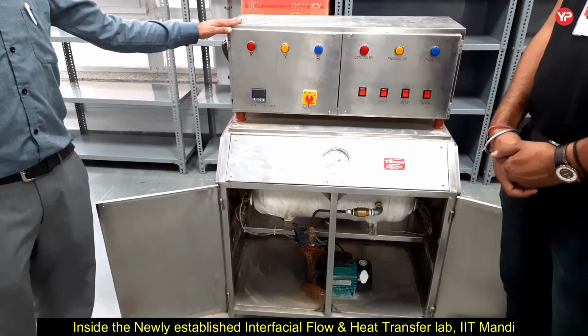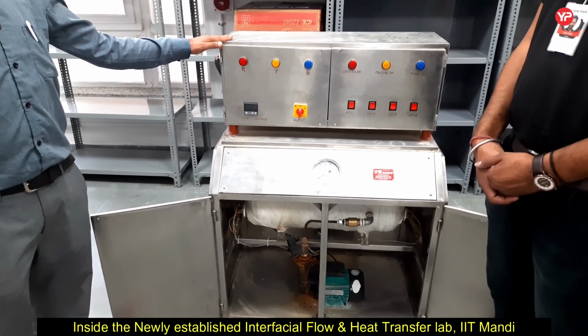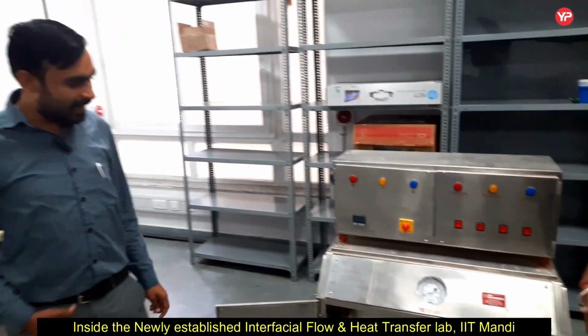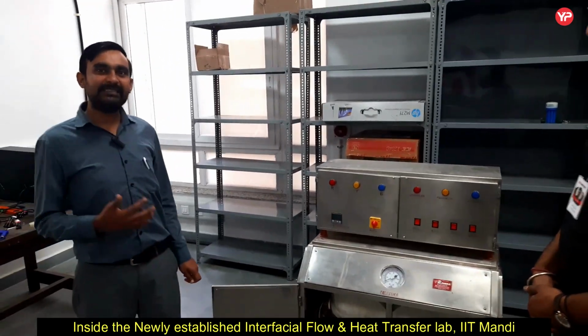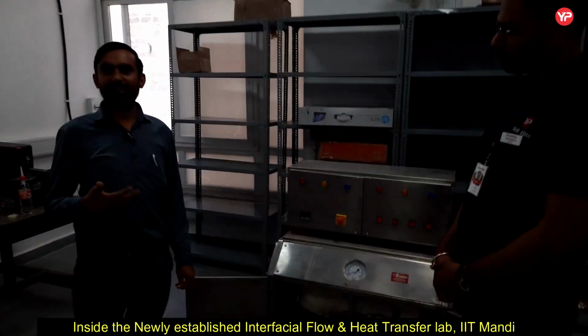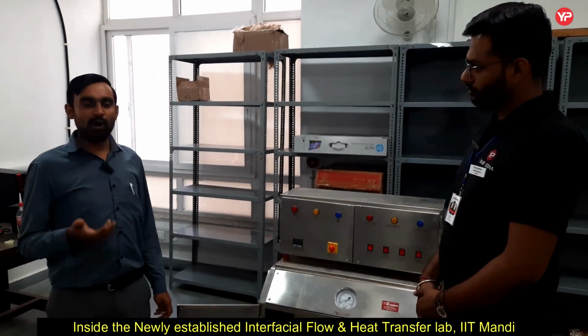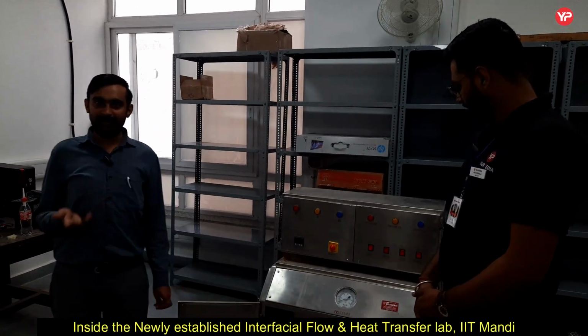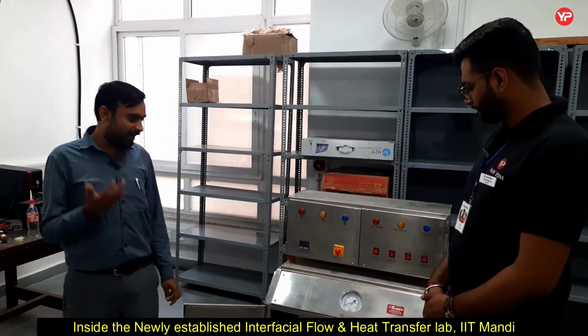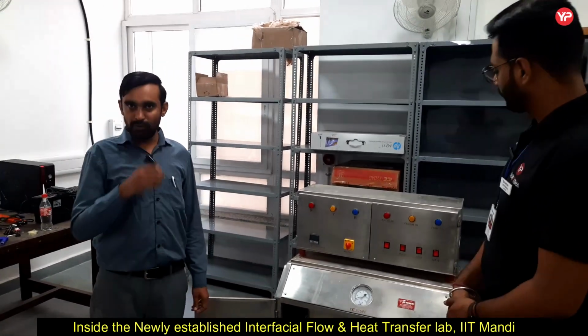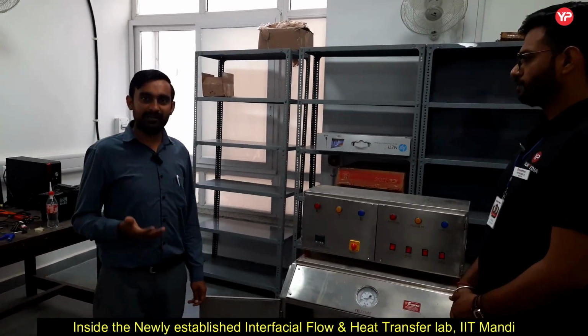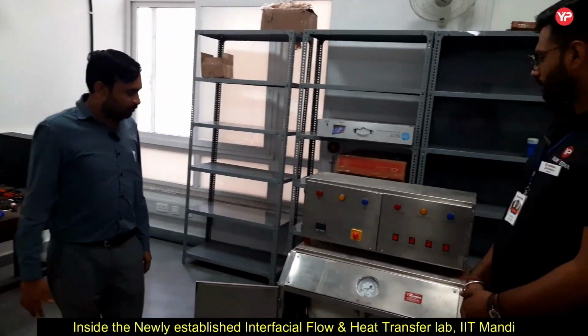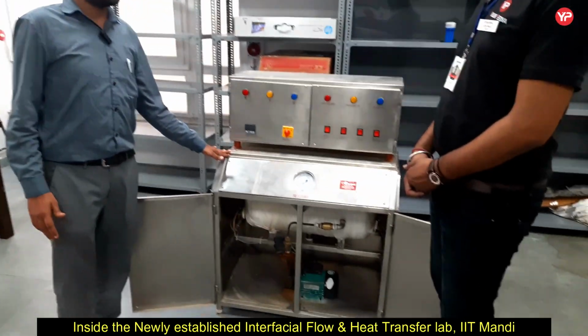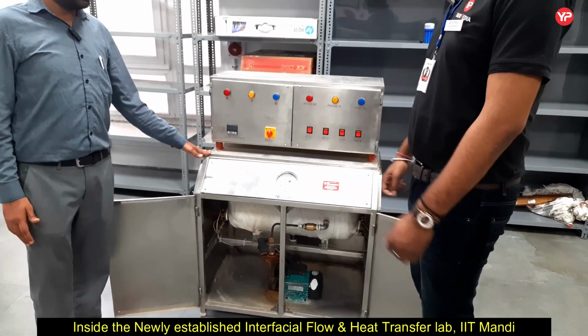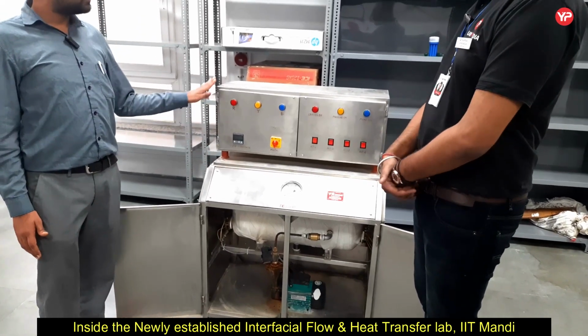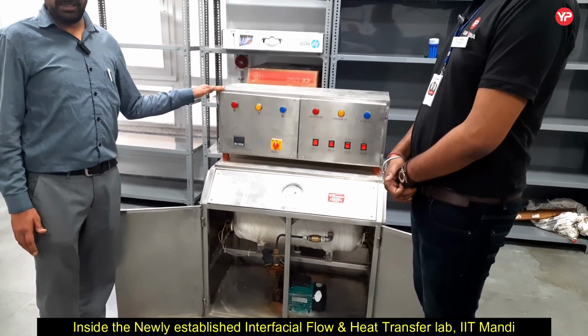This is called a non-IBR boiler. Basically a boiler which has its drum volume less than 24 liters is called a non-IBR boiler. IBR refers to Indian Boiler Regulation. If any boiler has its drum volume above 24 liters, then it has to be registered as per Indian Boiler Regulations. But this particular boiler is of smaller capacity, so such standards are not needed. That's why we call it a non-IBR boiler.